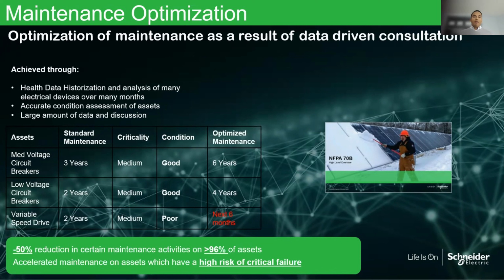Well, through data historization — which is really what we're doing at the very basic level — we're able to accurately assess the condition in which the assets are operating, in terms of environmental conditions, loading conditions over time, and operation conditions. So has the breaker opened and closed, for example, how many times, and how many amps when this breaker opens and closes?